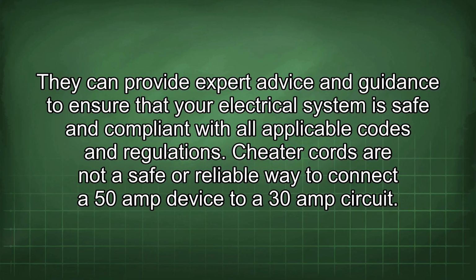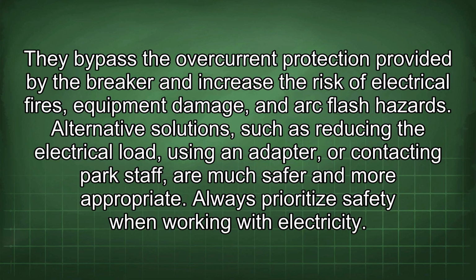Cheater cords are not a safe or reliable way to connect a 50 amp device to a 30 amp circuit. They bypass the overcurrent protection provided by the breaker and increase the risk of electrical fires, equipment damage, and arc flash hazards. Alternative solutions, such as reducing the electrical load, using an adapter, or contacting park staff, are much safer and more appropriate. Always prioritize safety when working with electricity.